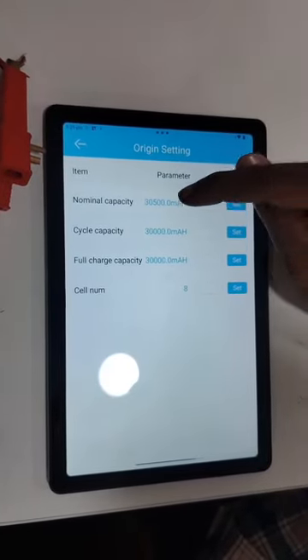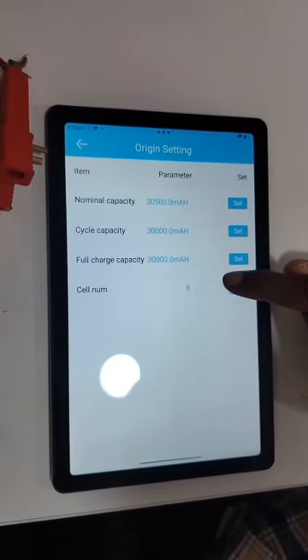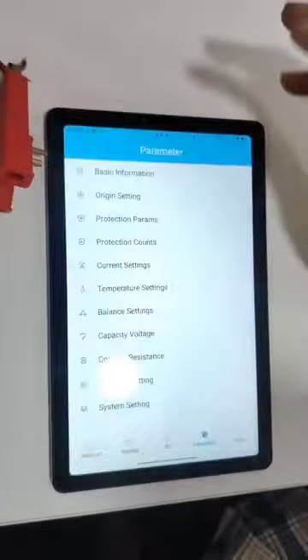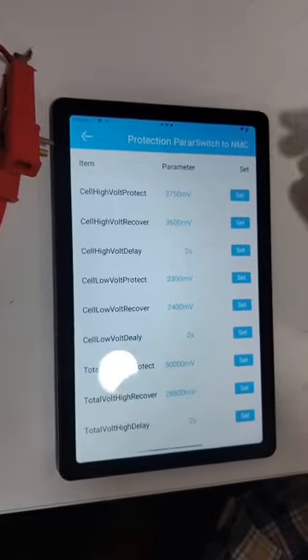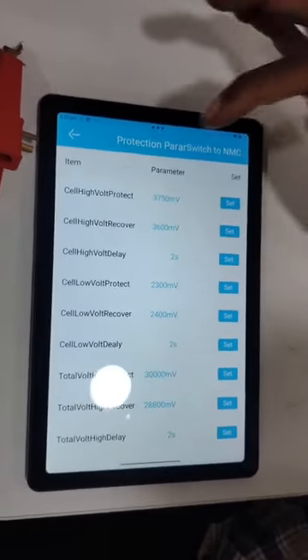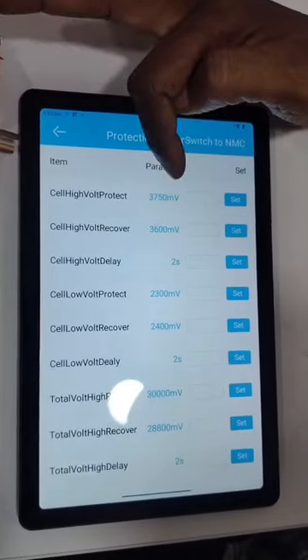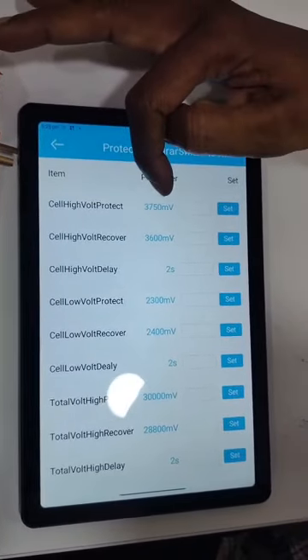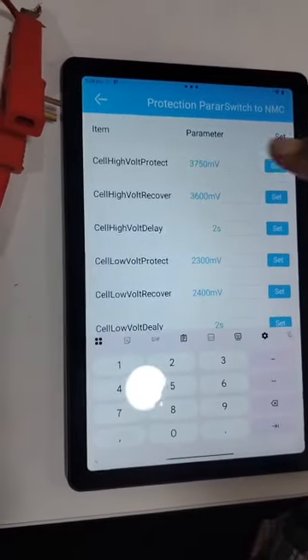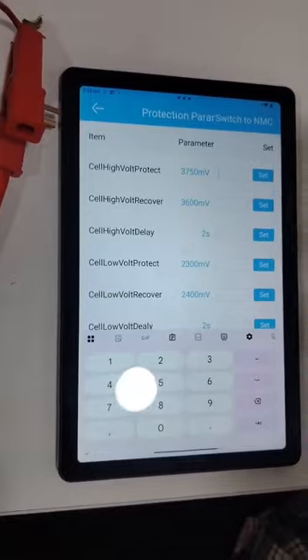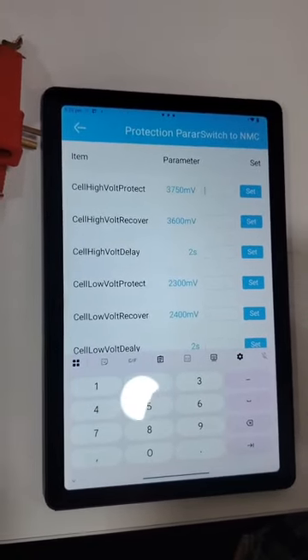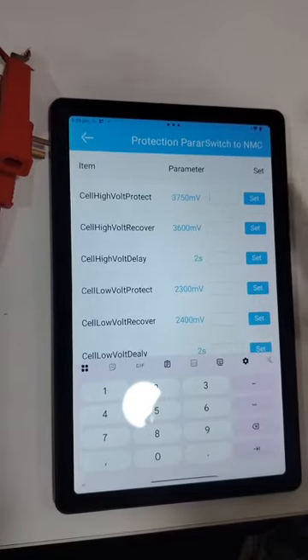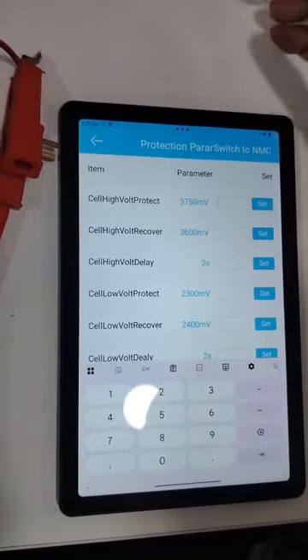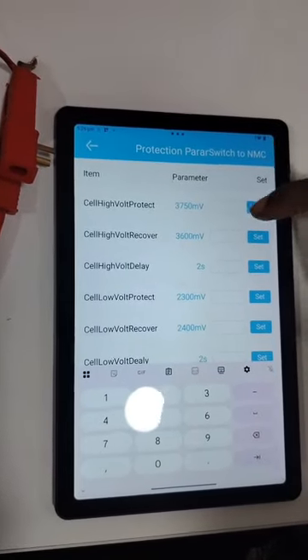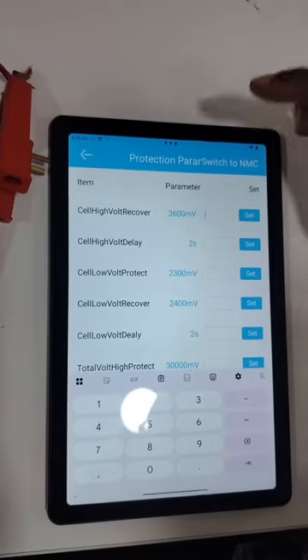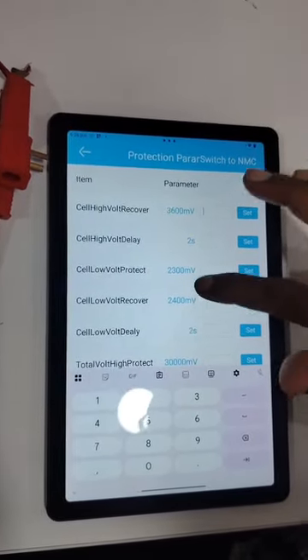What is the capacity of a complete battery, that you can feed here, then the cycle capacity, the full charge capacity, and the number of cells that you have to feed. Then protection parameter: what are the different protection parameters that you want to maintain. So here higher voltage protection is set to 3.75 volt. Okay, so you can change the value here if you want higher voltage, but it is always better to set below the prescribed limit. The manufacturer will prescribe a particular higher voltage protection limit as well as lower voltage protection limit, and you should keep that value below.